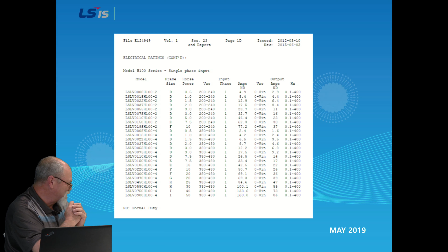Being that we have, like I said, the second largest testing facility, we have tested all of our VFDs on single phase power. We have a UL file. If you look, it will show that at 240 volts, I can operate X amount of amps. At 460, which you'd be surprised, is big in the irrigation industry, but in my history, to give an example, in the Shenandoah Valley there was no three-phase power. So all their pump stations were rotophases and so on and so forth, trying to reduce the cost or use three-phase motors. We now have the UL file, where a lot of my competitors say, oh, rule of thumb, just double the drive. But we have actually tested and can give you test data.